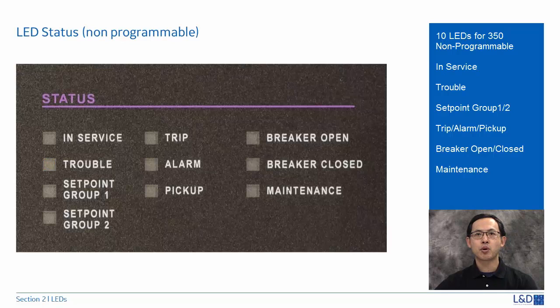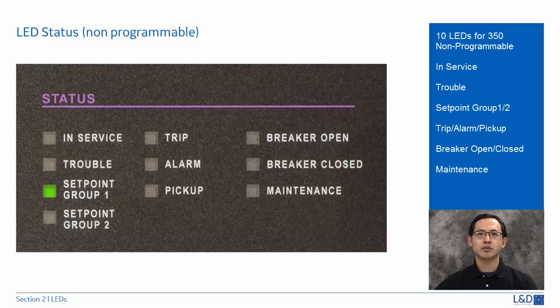Set point group 1 or 2 LEDs will turn on to green color to indicate the group of active protection elements. If set point group 1 is lit green, only the protection elements under group 1 will be active and the protection elements from group 2 will be inactive, and vice versa.